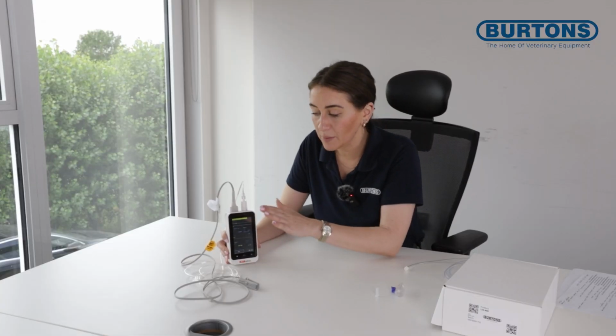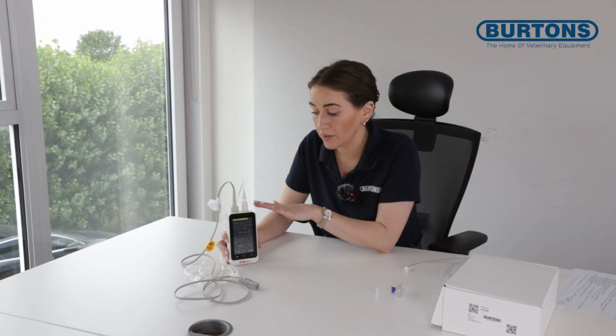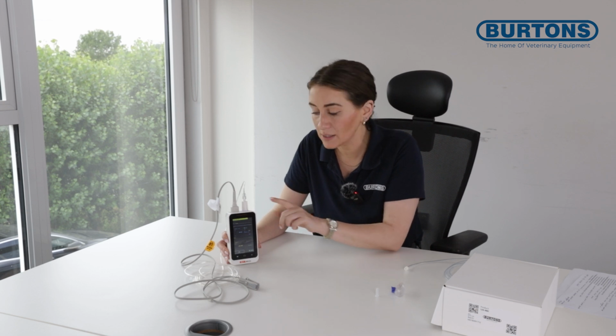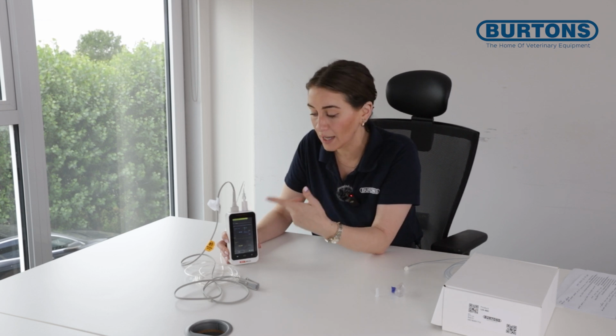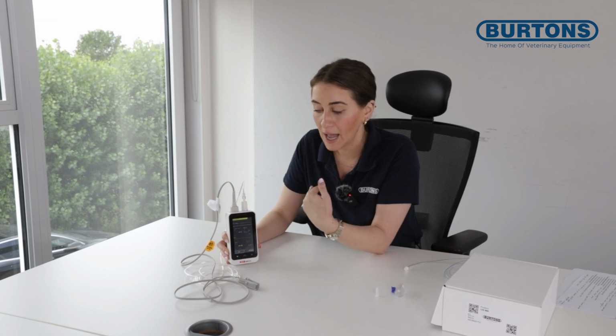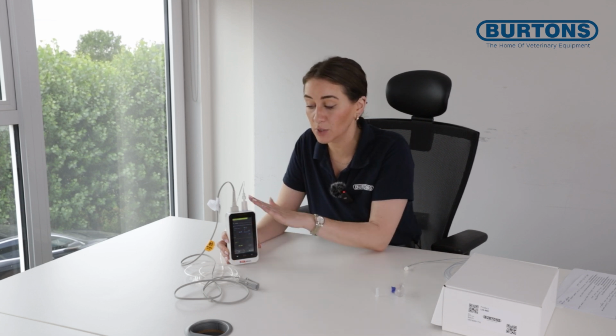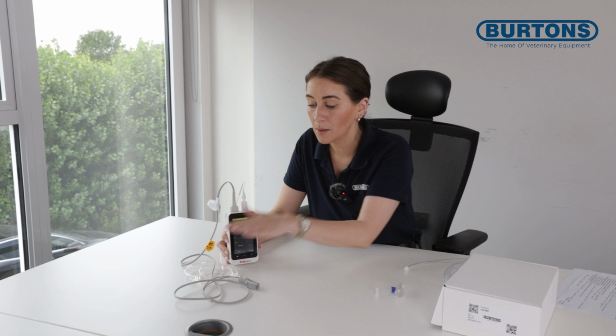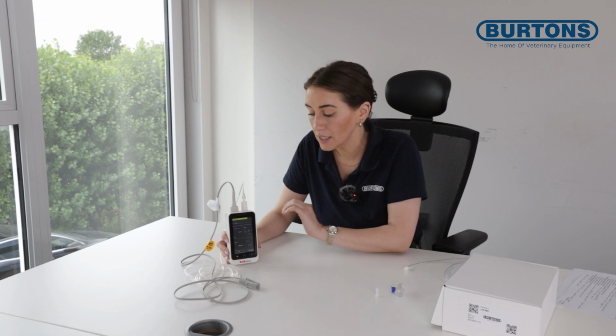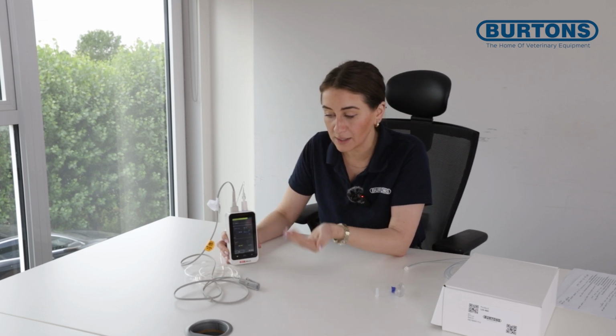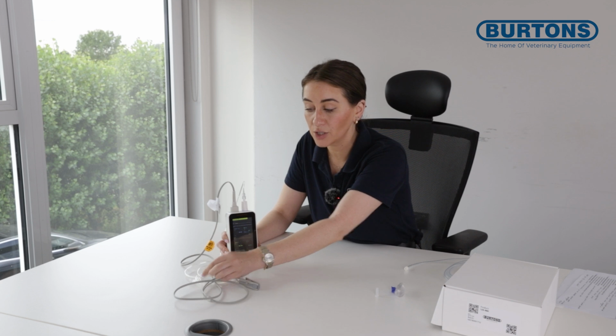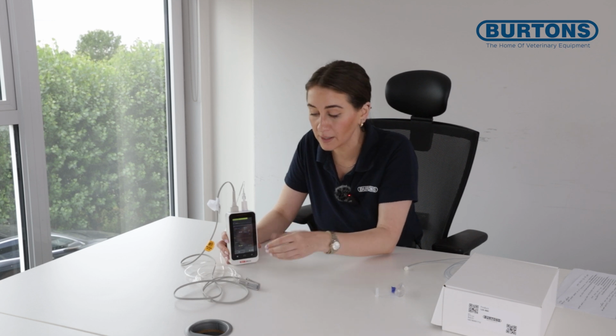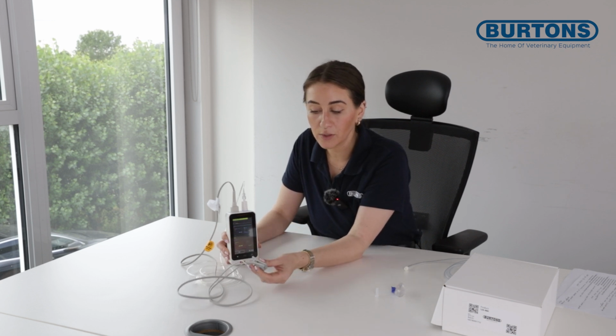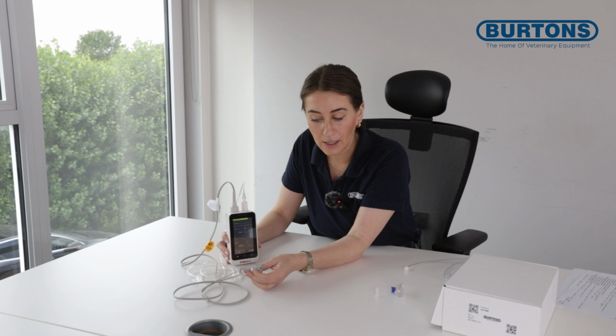So when we have the patient set up, we want to make sure that the machine has been turned on for at least 2 minutes, and that essentially is warming up the CO2 module internally to allow it to accurately measure as soon as we apply. So ideally, this machine is turned on 2 minutes prior to use, before being connected to our patient. So once we have that set up, essentially everything else is ready to go. We'll attach and we'll instantly get a capnograph form, and we can also attach our SPO2 probe directly as well.